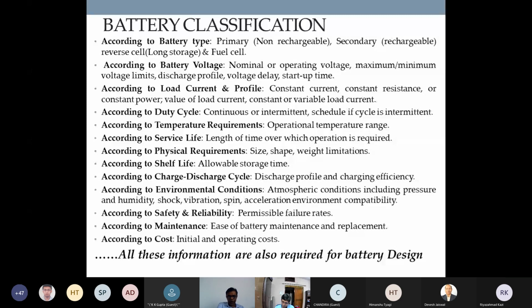Then one important point: what is the maintenance? A bad concept in our battery line is that we talk about sealed maintenance-free batteries rather than VRLA batteries. We say sealed maintenance free, but actually every battery requires some type of replacement or maintenance, whether it is lead acid flooded or tubular, nickel cadmium, lithium ion, or VRLA battery.